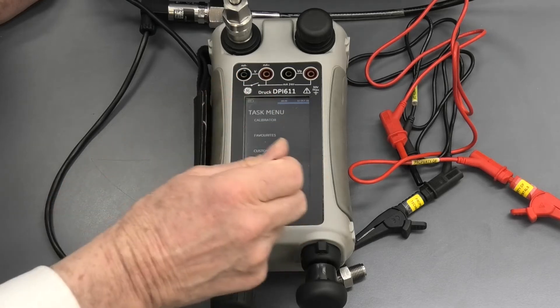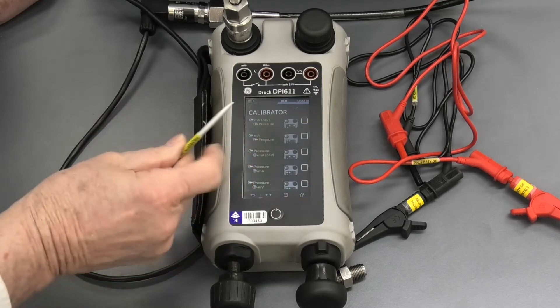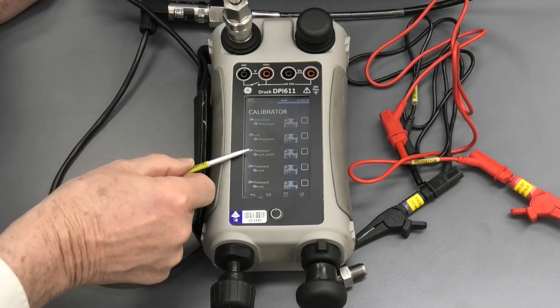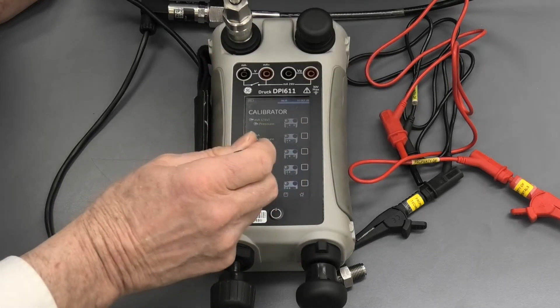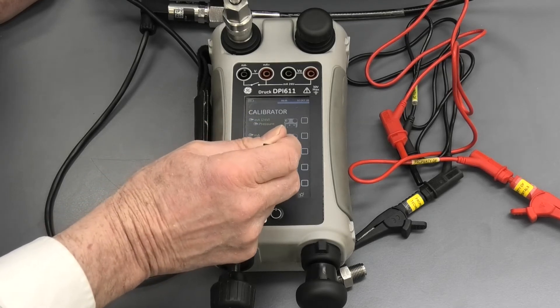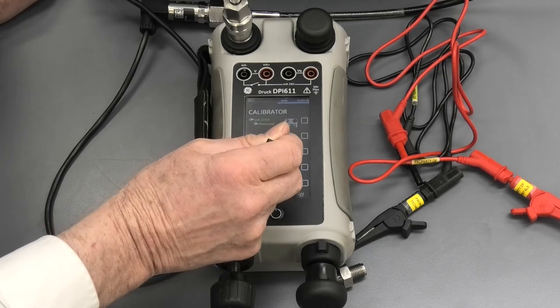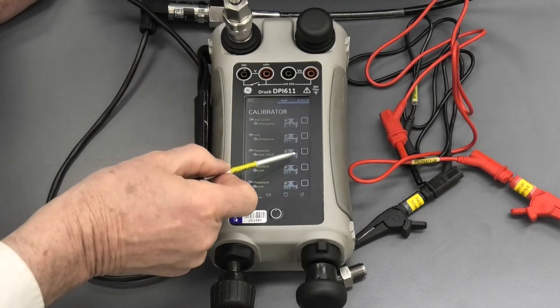Now, when I select the calibrator, it comes up. Now, in this instance, we want pressure out with 4 to 20 milliamp in, 24 volt supplied, because we don't have a power supply here. Now that also indicates how we're going to do the 4 to 20 milliamp wiring there. So it tells us we're going to be using this pressure point, which is correct.